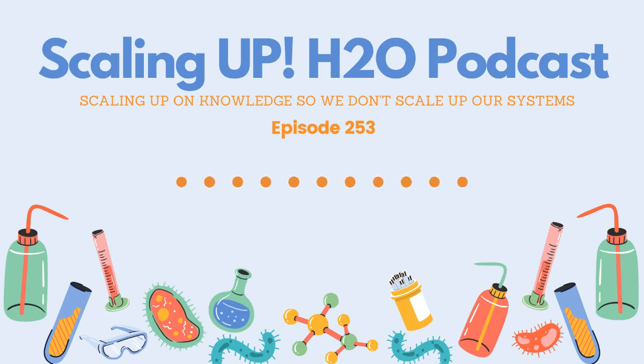Sure. This is a huge issue right now with water conservation efforts and the mandating of low-flow fixtures. The potential for biofilm growth is really expanded within these systems. There are two reasons for this. One is that the fluid shear a flowing system imparts helps drive the disinfectant into the biofilm, and that disinfectant in potable systems, here in the U.S. anyway, is overwhelmingly either chlorine or chloramine.